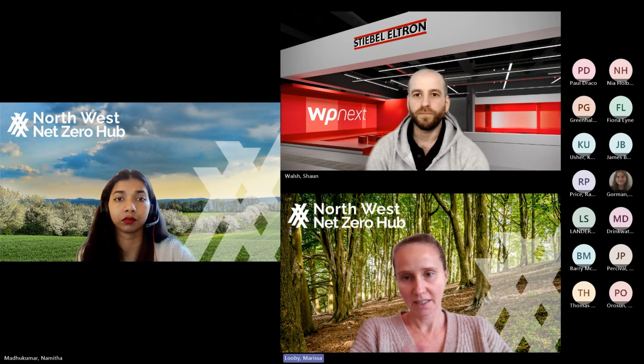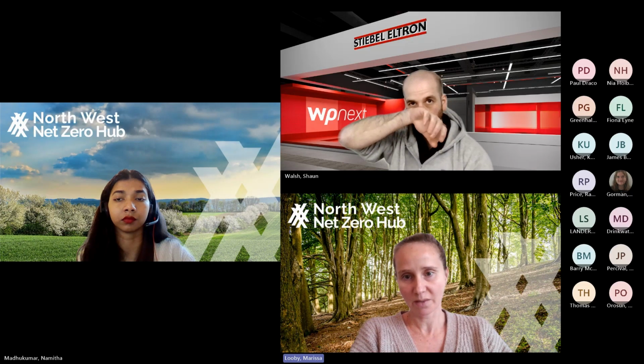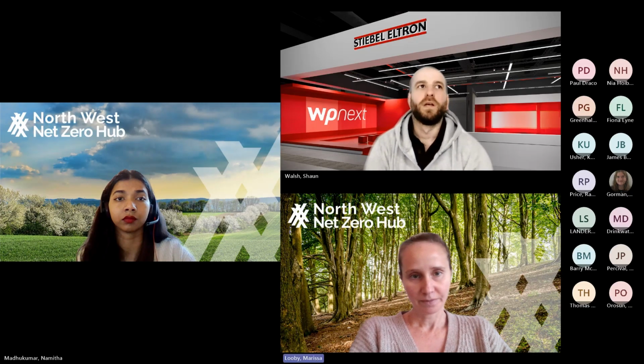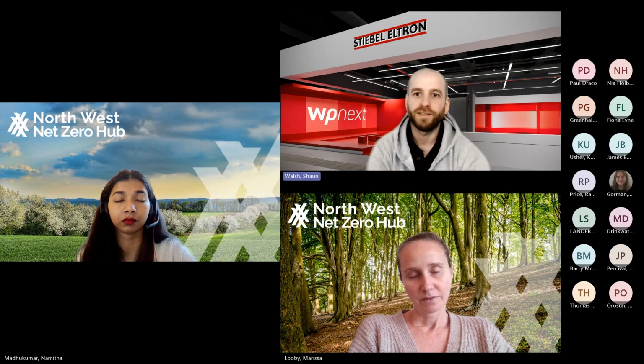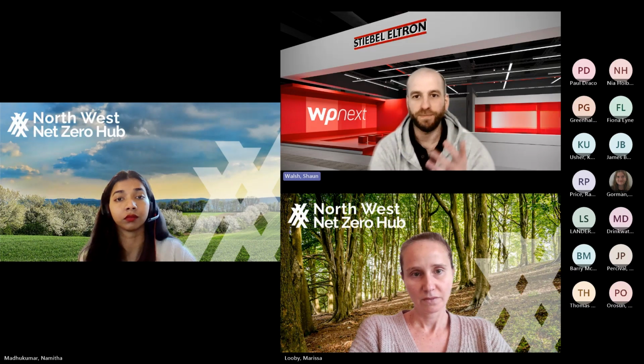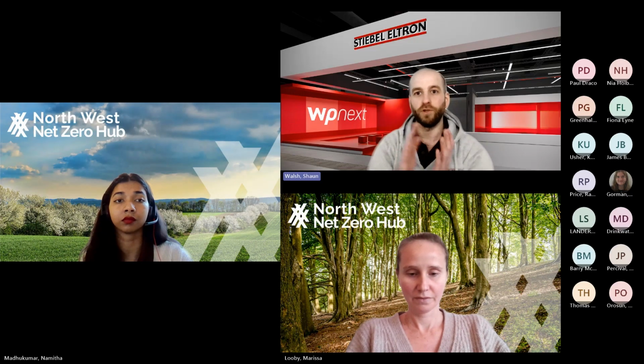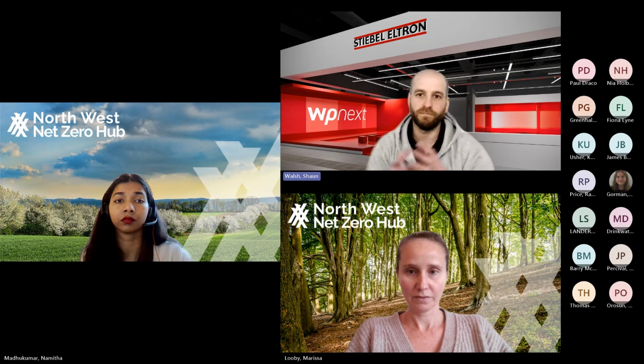Thanks. A little bit more on cost: on average, do heat pump systems have fewer maintenance issues and costs versus a gas boiler over a lifetime? If they're serviced correctly, they shouldn't require any more than the standard you would do on your gas boiler annually. You have your annual gas boiler check. If you're servicing an air source heat pump once a year, it should run fine over its lifetime, as long as the servicing and maintenance is done correctly. So yeah, it's similar. Do it annually, maintain it correctly, and you shouldn't have any problems.